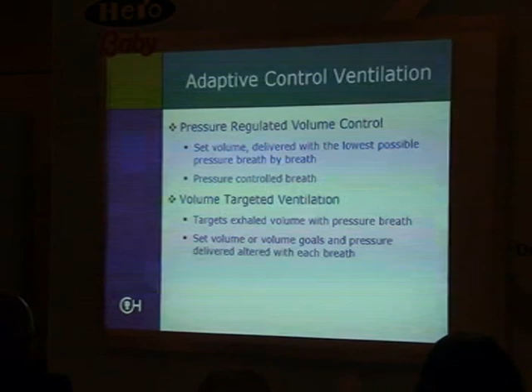Volume targeted ventilation is another way of saying this. Each ventilator company has their own name for the same type of mode. They have it trademarked so nobody else can use it, but they all pretty much do some of the same things. So pressure regulated volume control is one of them. Volume targeted ventilation is another. Volume guarantee is another name for them. Volume targeted ventilation targets the exhaled breath from the prior breath to set the pressure for the next breath going forward. But still, you're setting the volume that you want delivered, and it is a pressure-controlled breath that is being delivered to the patient every single time with each breath.